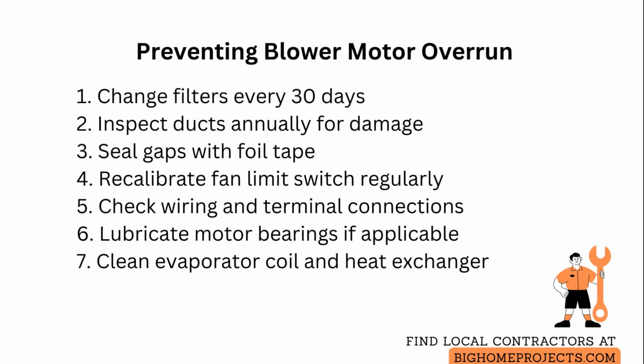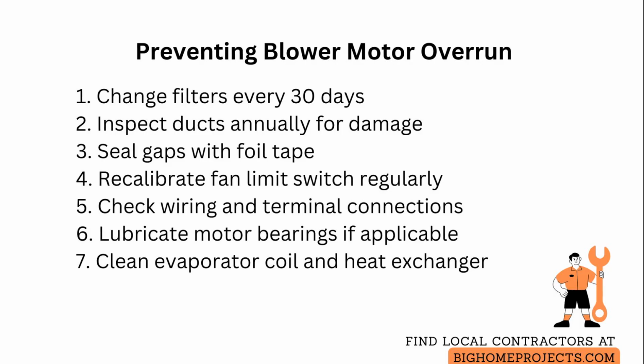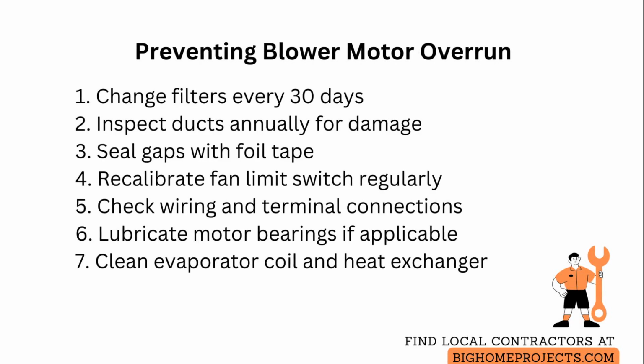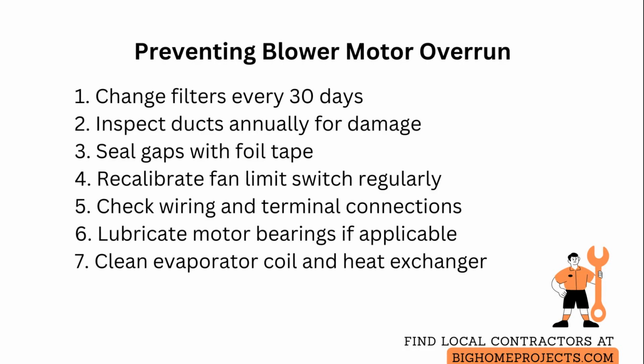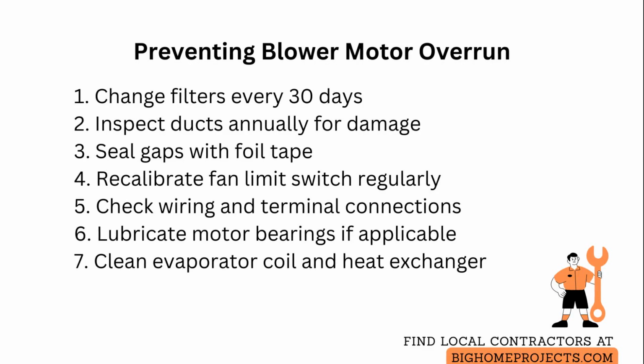Recalibrate the fan limit switch every 2 to 3 years, or whenever you replace the thermostat, by first cutting power, removing the furnace access panel, gently adjusting the switch to the manufacturer recommended range, and verifying that the blower turns off at the correct temperature on the heat cycle and on during the cooling cycle as required.